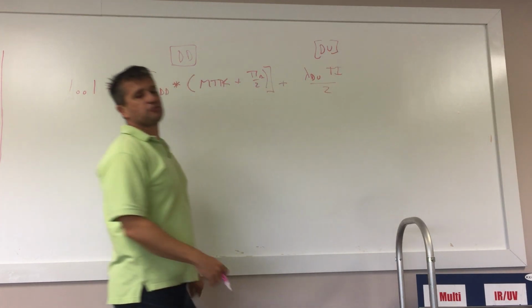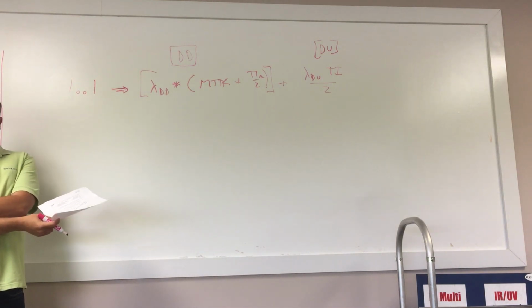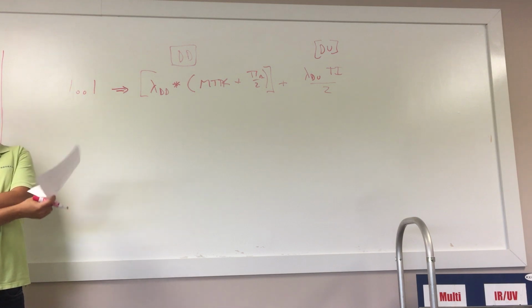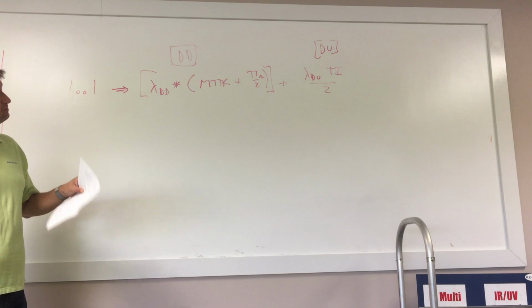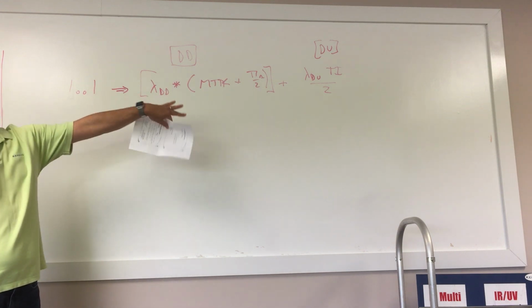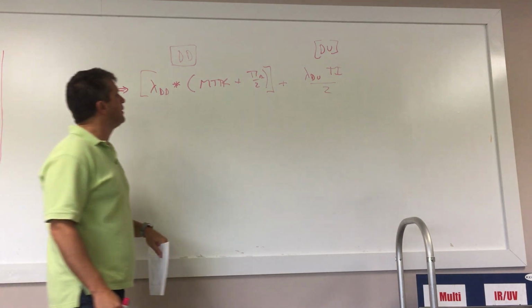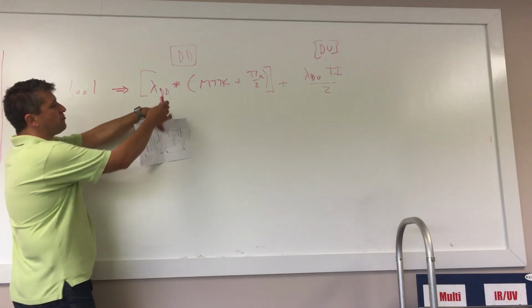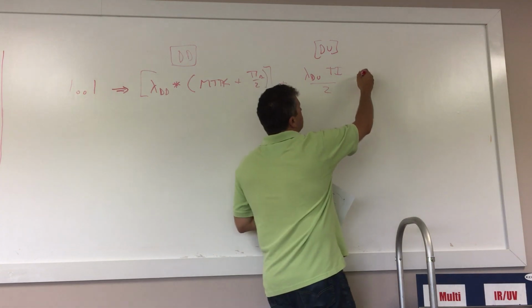This term is related to the unreliability of the safety instrumented system due to failures that are not detected with automatic diagnostics. You will not know about them until the safety instrumented function fails. That term is always there. That is the one term that is never ever going to go away. And you'll see this is in the format of lambda T over 2, whereas this is in the format of lambda MTTR. I will come back to that.